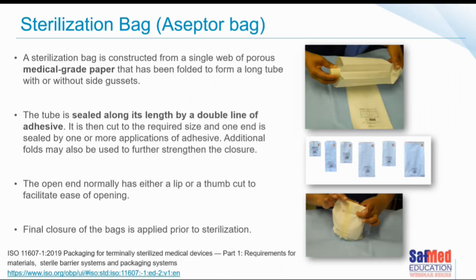A sterilization bag — for example an Aseptor bag — is constructed from a single web of porous medical-grade paper, folded to form a long tube, available with or without gussets. A gusset makes the bag able to open wider for broader items. The tube is sealed along its length by a double line of adhesive, then cut to the required size. One end is sealed by adhesive, and additional folds are used for further strengthening the closure — corner, corner, fold over, fold over, fold over. The open end sometimes has a lip to facilitate ease of opening, and the final closure is applied prior to sterilization.